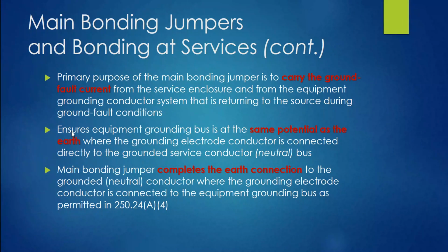All right, so next, it ensures that the equipment grounding bus is at the same potential as the earth, where the grounding electrode conductor is connected directly to the grounded service conductor. All right, so let's discuss that again. So at that panel, it's typically the location, and we're not talking about the wire type that connects to a separate equipment grounding bus here. We're talking about the traditional one that you see. And we'll see some graphics in a minute, and I'll point that out.